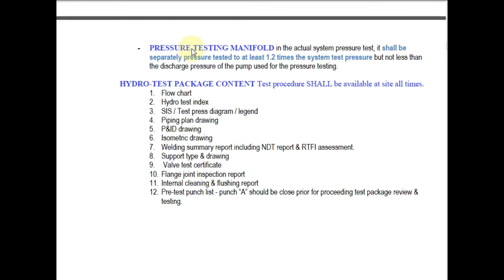Hydro test package content. Test procedure shall be available at site at all times. 1. Flow chart. 2. Hydro test index. 3. SIS test pressure diagram legend. 4. Piping plan drawing. 5. P&ID drawing. 6. Isometric drawing. 7. Welding summary report including NDT report and RTFI assessment. 8. Support type and drawing. 9. Valve test certificate. 10. Flange joint inspection report. 11. Internal cleaning and flushing report.